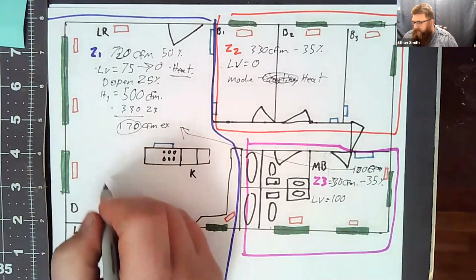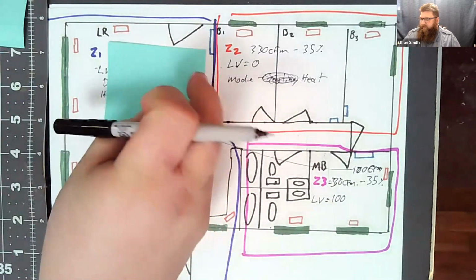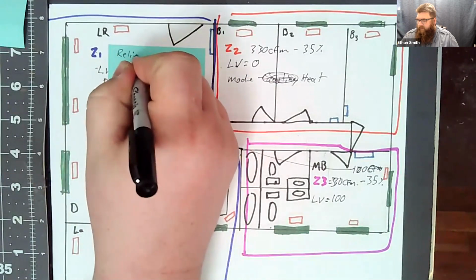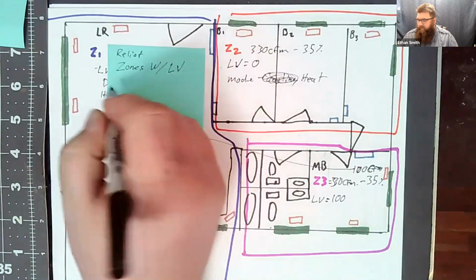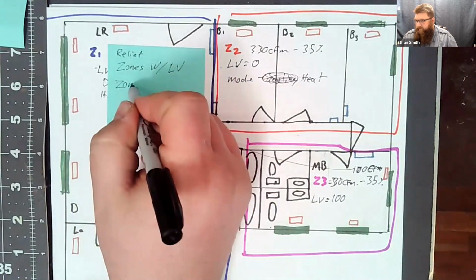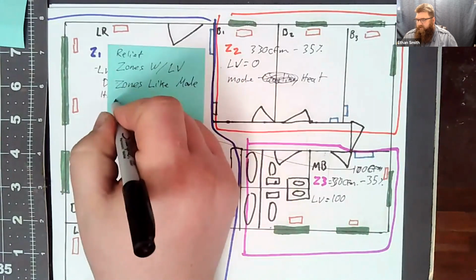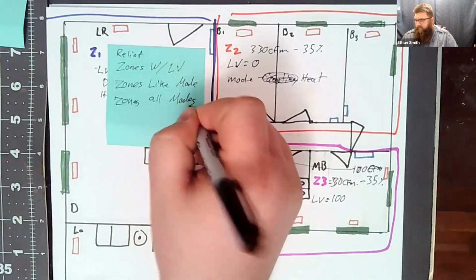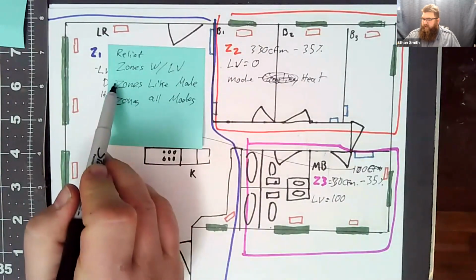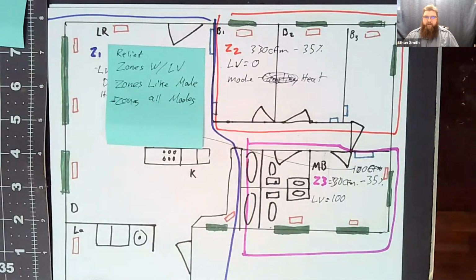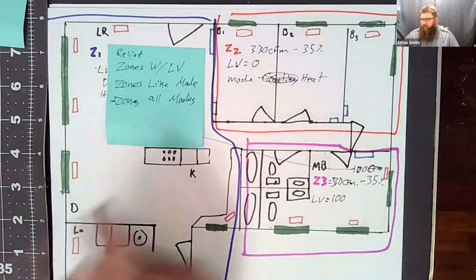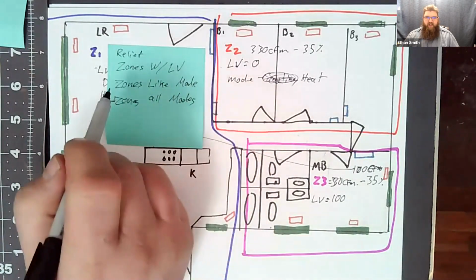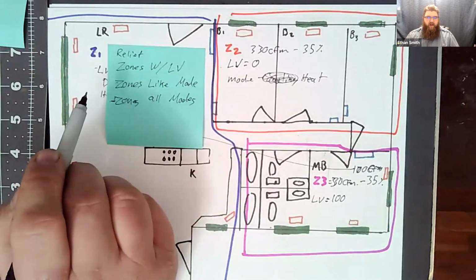So it prioritizes relief air in 3 steps. Those priorities are to zones with load value, then zones in like mode, and then zones in all modes. Like I said, very rarely do we get here. We almost never get here if we've done our job right. Okay. In order to get here, we're going to have to open all the zones with load value to 100% and still have excess air problems. I have seen this happen.